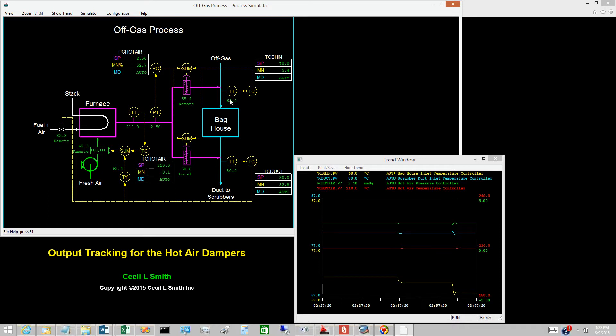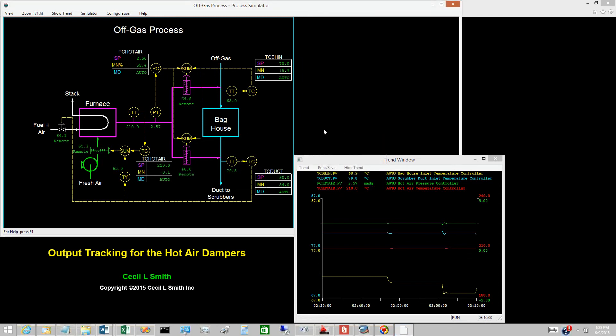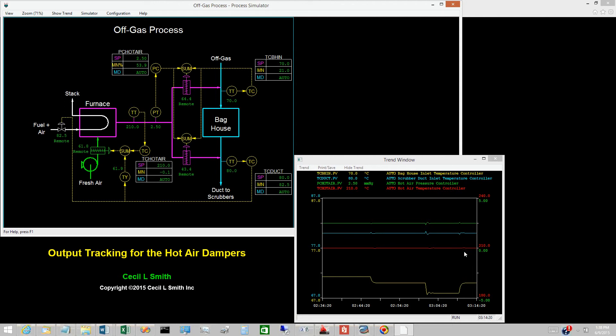To show that the transition back to automatic control is bumpless, switch the damper back to remote. The baghouse inlet temperature controller takes the necessary control actions to restore the temperature to 70 degrees Celsius. This controller is aggressively tuned, but the transition is smooth.